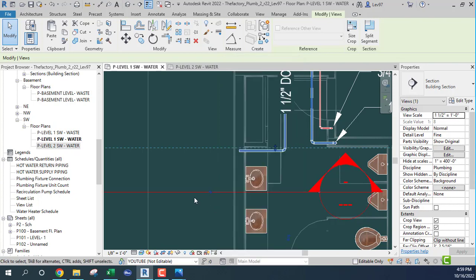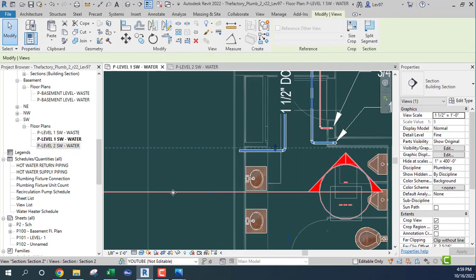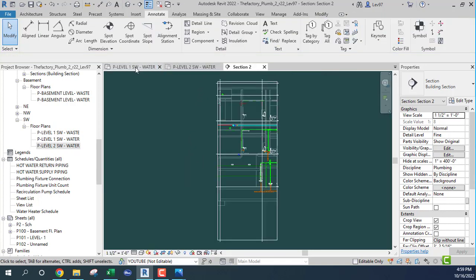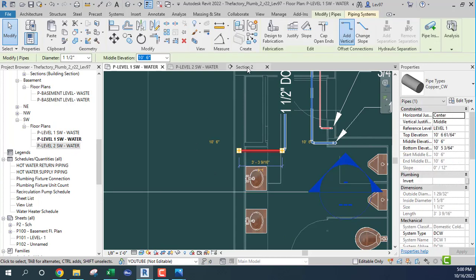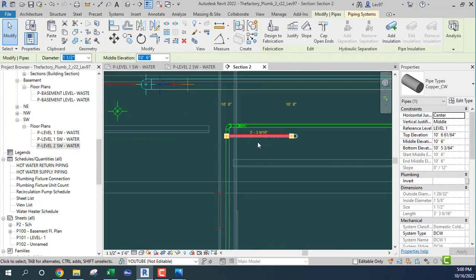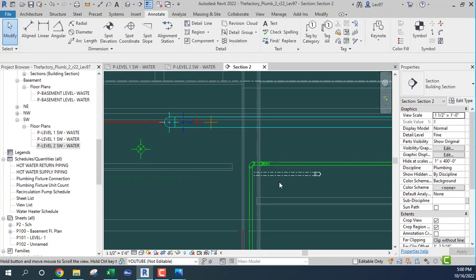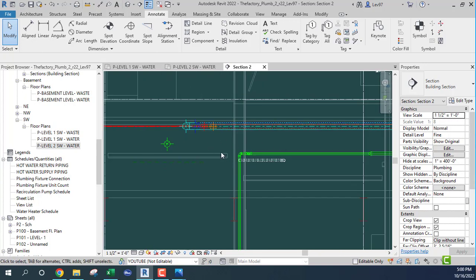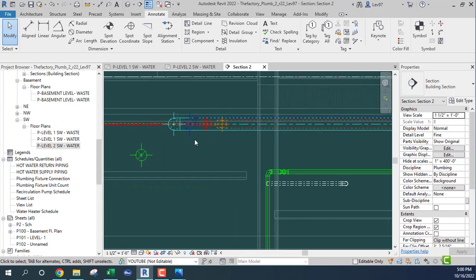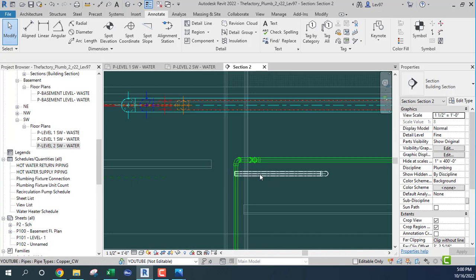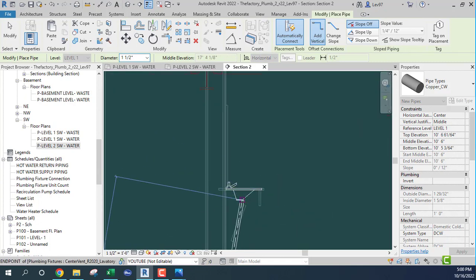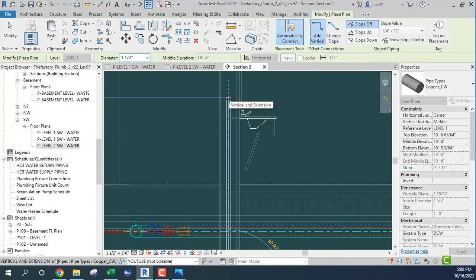I right-click, hover over my section, right-click and go to that view. Let's get a reference here — go to that view and I am here. There's some interference with the mechanical but anyway, we're going to go up to about right here. You don't want to go above that because you're wasting pipe.